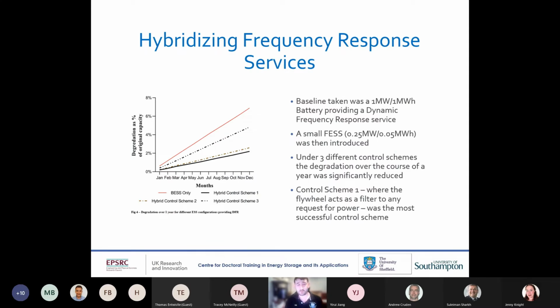One of the applications I've looked at is hybridizing frequency response services. As I said, there's a vast amount of already deployed battery energy storage systems across the country. We took a baseline of a 1 megawatt hour battery providing a dynamic frequency response service 24/7, and then introduced a small flywheel into that system to try and take some of the strain off the battery. On the baseline, the battery was experiencing around 6.8% degradation per year, which is quite significant and could easily affect the economics of the site.